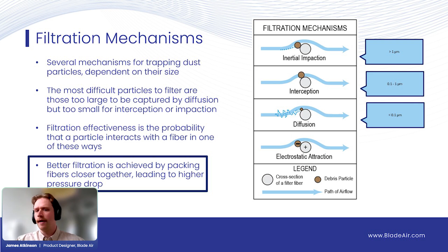Now, electrostatic filtration is a bit different. This actually creates a force that attracts dust to the fiber, so you don't have to pack the fibers as close together, because the radius around the fiber in which dust will be captured is larger. You're creating a force that pulls dust into your fibers.